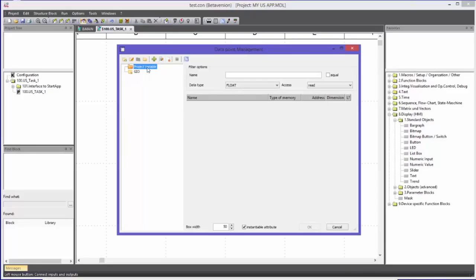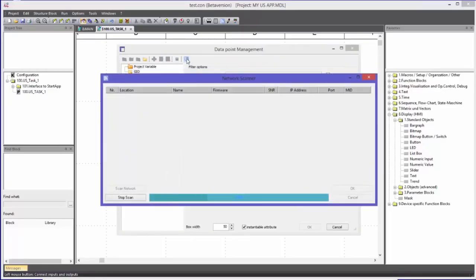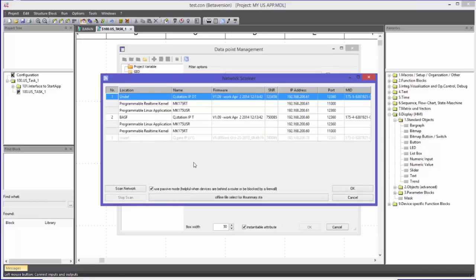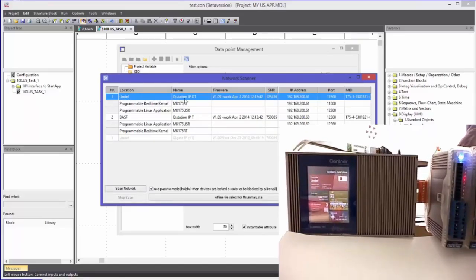Subsequently the data point management opens. You can see the project variable section, which is still empty as we have not yet created a project variable. You can also see the section GIO or Gantner IO, which is also empty because we have not yet made a connection to the QStation — the app connectors are not visible yet. Over the command Import Gantner IO I will now scan the office network. The scan dialog opens and the system finds three controllers. I will select the user kernel.